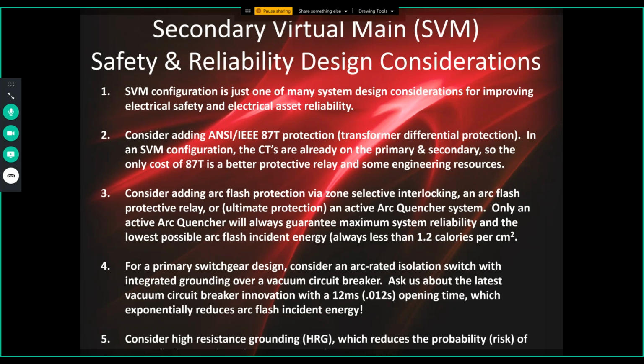And for primary switchgear design, if you're going to use a secondary virtual main, and now you have a device on the primary side of the switchgear you could control, one of the things you can ask us about is a breaker with a 12 millisecond opening time. So this is orders of magnitude faster than the next fastest 3-cycle or 50 millisecond breaker on the market. If you take that 12 millisecond opening time for the breaker and add an arc flash protective relay to it, your total clearing time will be less than 16 milliseconds. You have better than less than one cycle total clearing time in terms of arc flash incident energy.